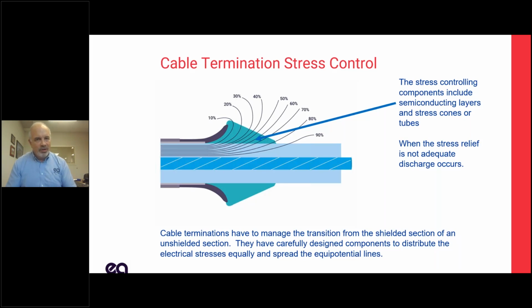So what we have are these stress control products: terminations, stress cones, cold shrink terminations, hot shrink terminations. They get a variety of different terms, but the whole purpose of them is to take these electric field lines, which are very close together in the insulation because it's controlled, and spread them out as they go to the totally uncontrolled air around the cable. You'll see something that might be a geometric shape, or it might have different stress control properties within the tube itself. The tube may be just a rectangular tube, but it has varying different permittivities in it.